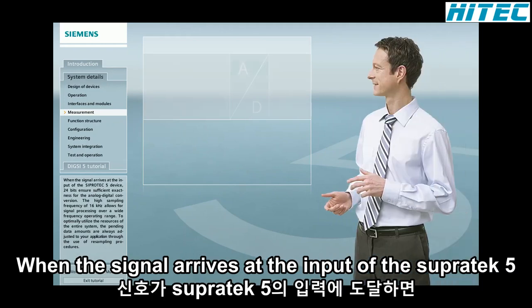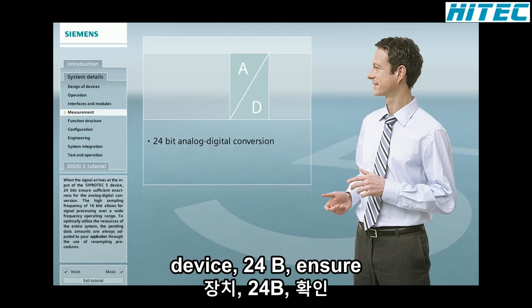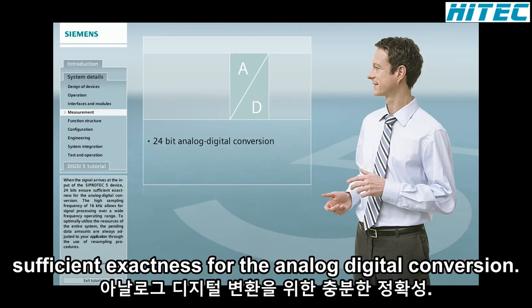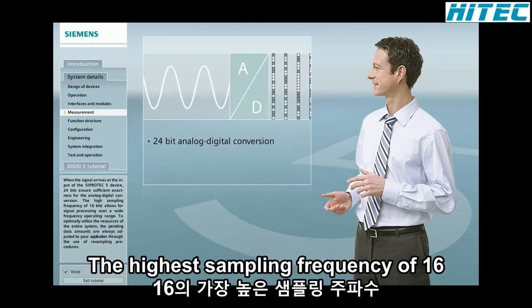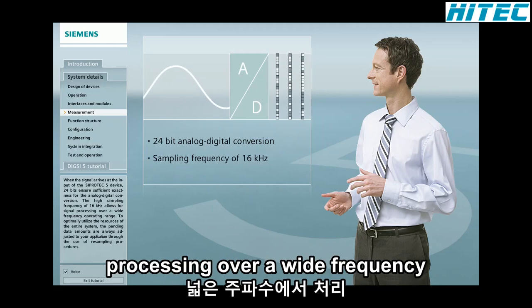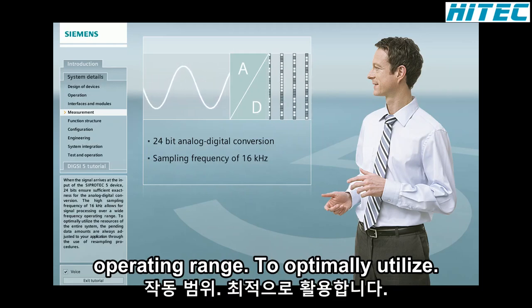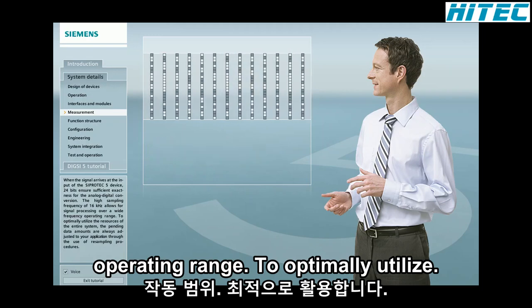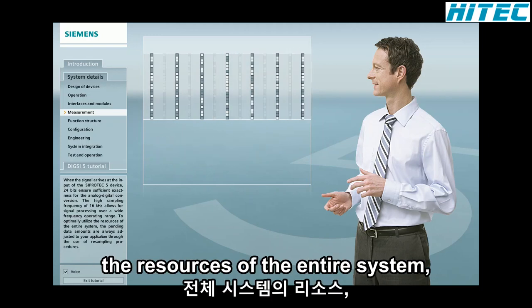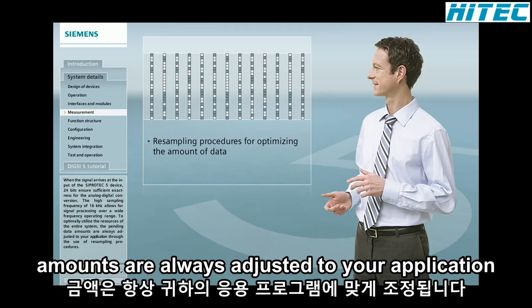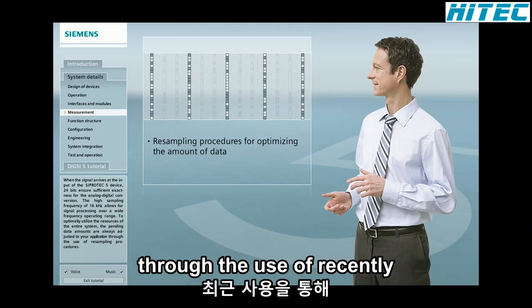When the signal arrives at the input of the SIPROTEC 5 device, 24 bits ensure sufficient exactness for the analog-digital conversion. The high sampling frequency of 16 kHz allows for signal processing over a wide frequency operating range. To optimally utilize the resources of the entire system, the pending data amounts are always adjusted to your application through the use of resampling procedures.